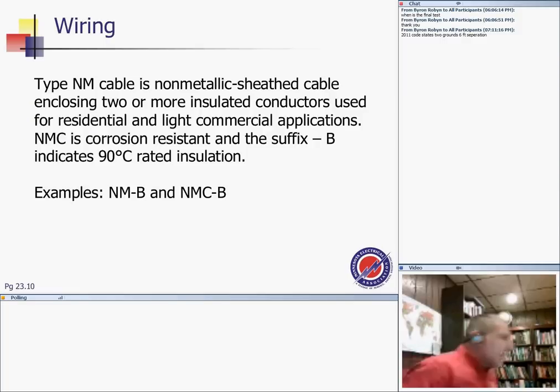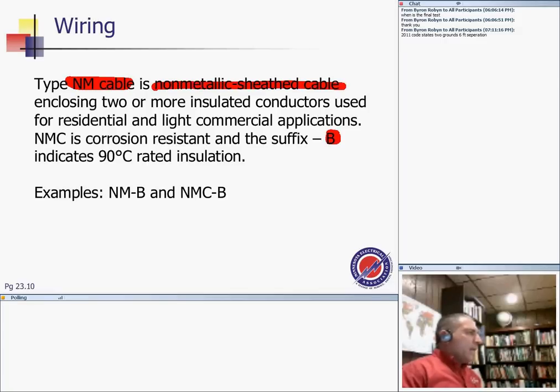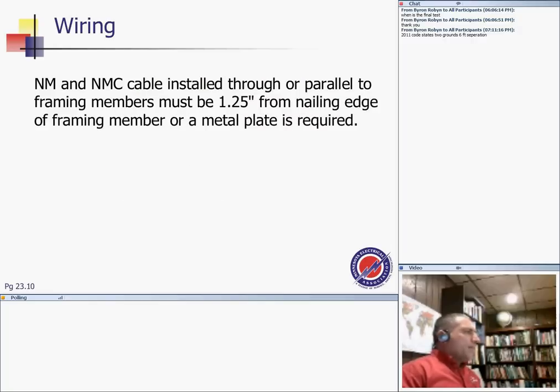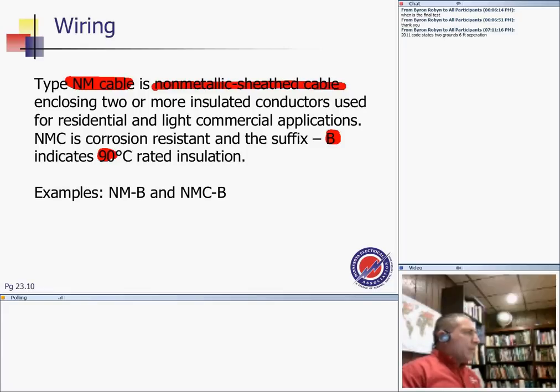Now, wiring residential, my friends. We talked about Romex, guys. The single most important cable that you're going to be using in residential is NM cable. Use it 95% of the time. Non-metallic sheathed cable, if it has a B, it stands for 90 degrees, meaning the insulation inside it is 90 degrees. Just a quick reminder, guys, because that's the most important wiring method, at least in Minnesota, that we use.